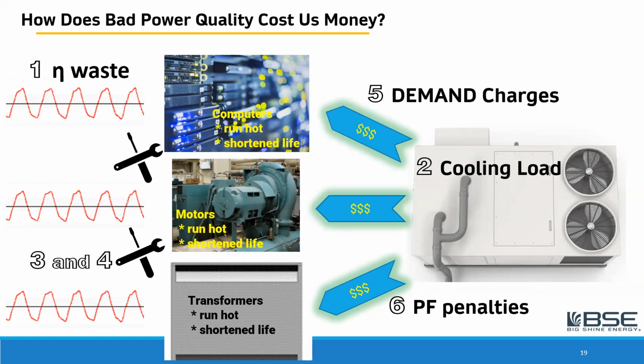Well, first of all, during the summer, if we have equipment that's running hotter than it needs to be, we're going to pay money right away with the higher cooling load. We have to cool off the building to keep everybody comfortable, but now we're cooling a bigger heat load inside the building than we otherwise would have. But then also, if we shorten the life, out of the blue somewhere, a motor will fail, or a server will go down, or a transformer will go bad. It's not very often, but these things become very expensive and they're big disruptions to our operation. So 3 and 4 are meant to indicate both the direct and the indirect consequences of unplanned outages and premature failure. And then finally, demand charges.